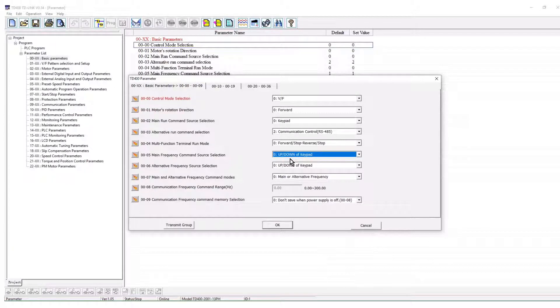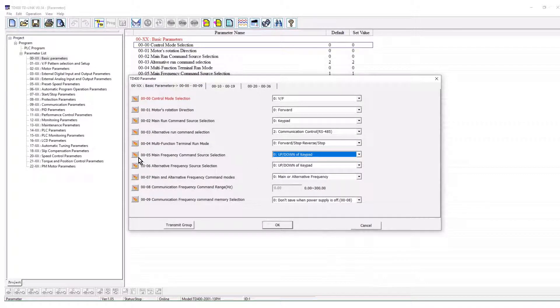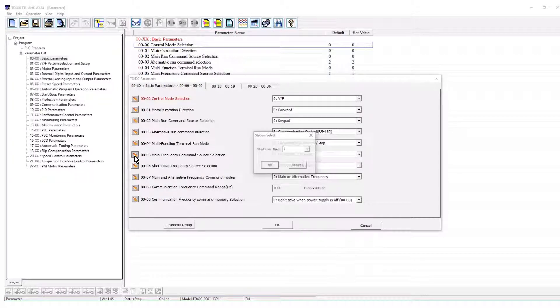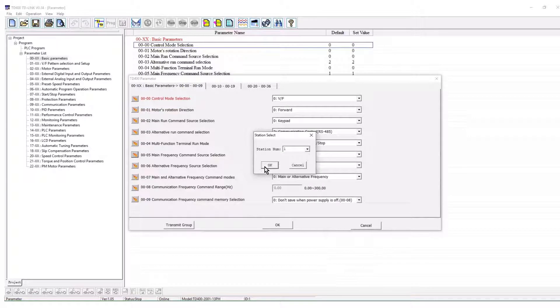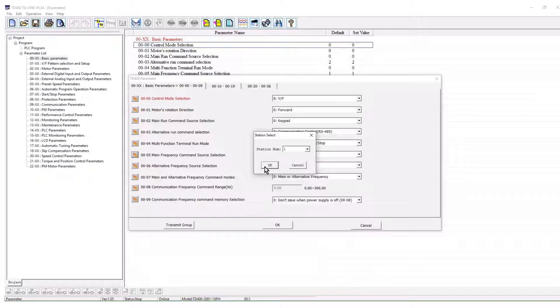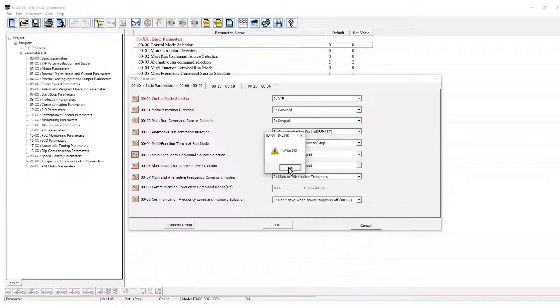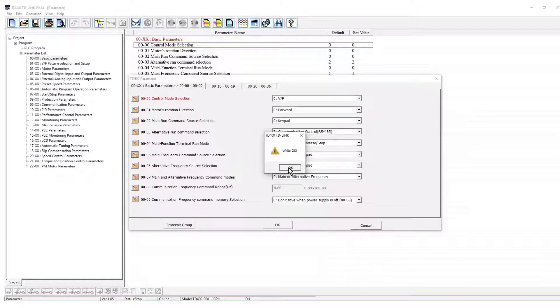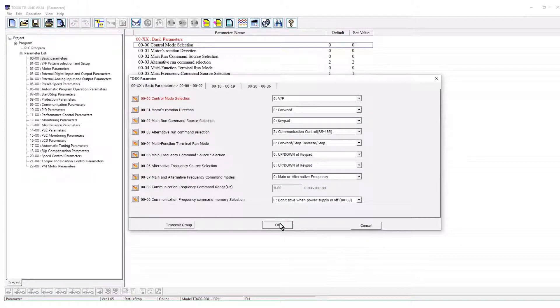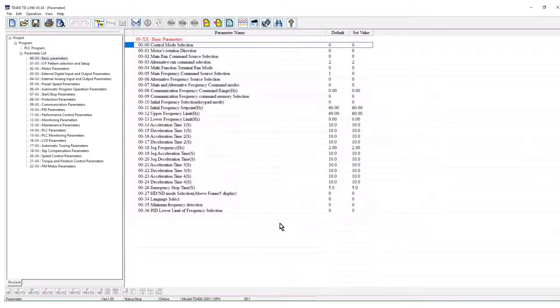One parameter at a time can be written by clicking the arrow to the right of the parameter. The station or node number can be selected. We are using only one VFD, station number 1. Click OK. The successful write will be indicated. Click OK again to exit parameter group 0.